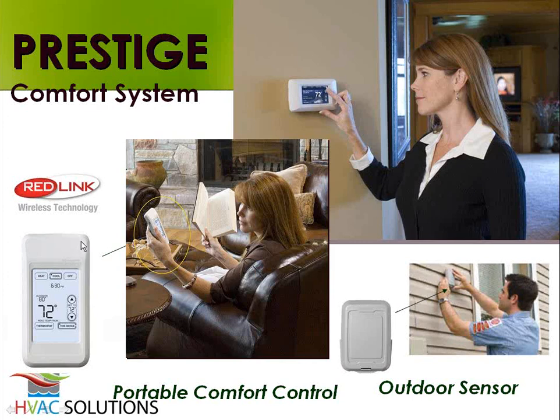And then on the left-hand side of the screen, the personal portable comfort control, which is a handheld device. So you can adjust your thermostat from anywhere, from your couch, from your nightstand, from your kitchen, wherever. That's what that guy's going to do. So the Prestige can talk to actually 3 different devices wirelessly. This is 2 of them, the personal portable comfort control and the outdoor air temperature sensor. But he would be hardwired to the furnace itself.